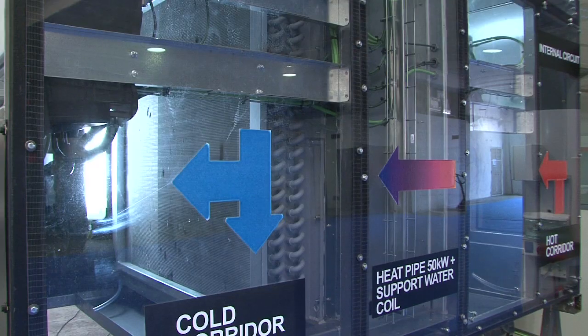There are 3 basic stages of operation on this unit. Stage 1 is when the air-to-air exchanger is providing full load. This means that in order to provide 24 degrees on the cold corridor, the external air as an average has to be 20 degrees Celsius or lower.